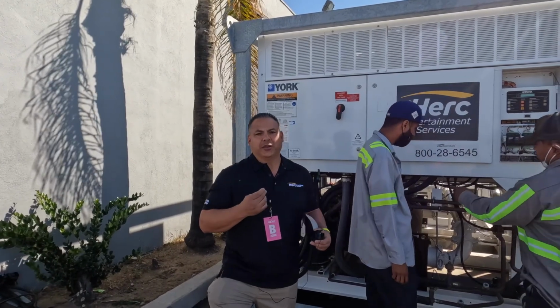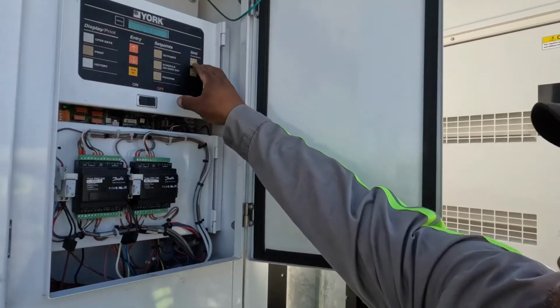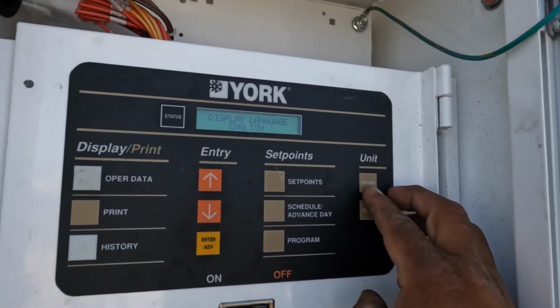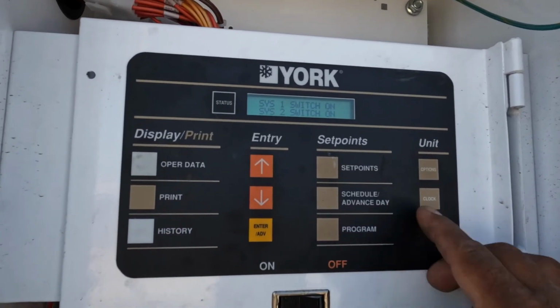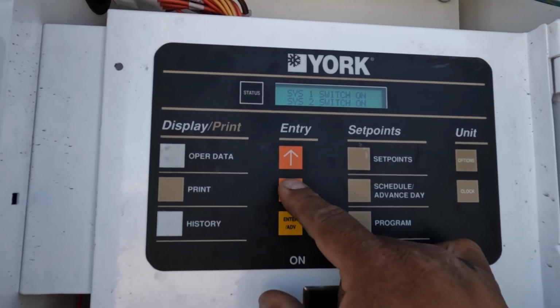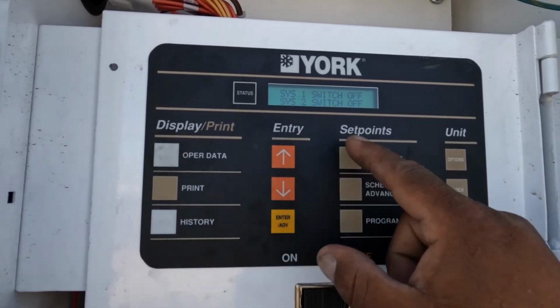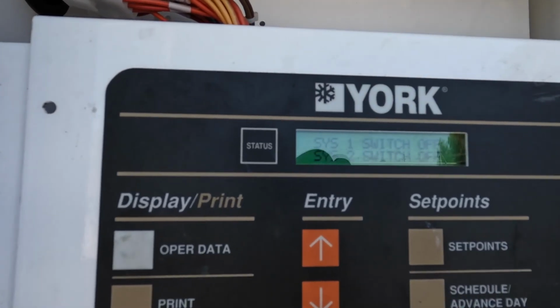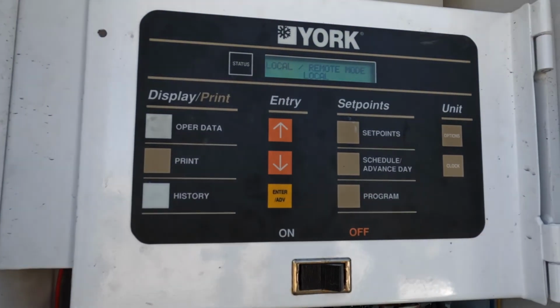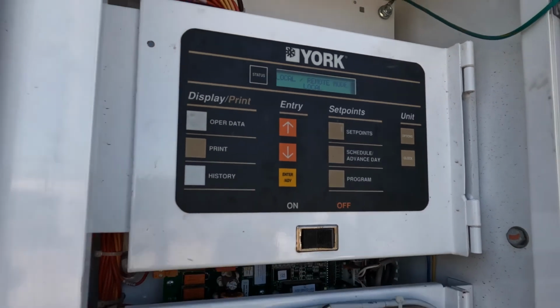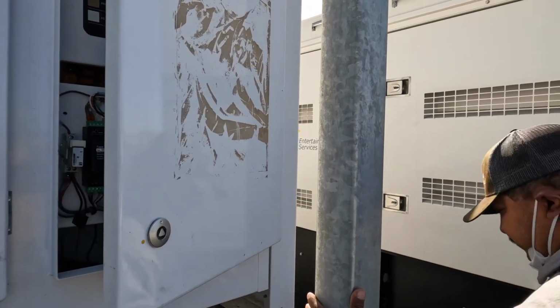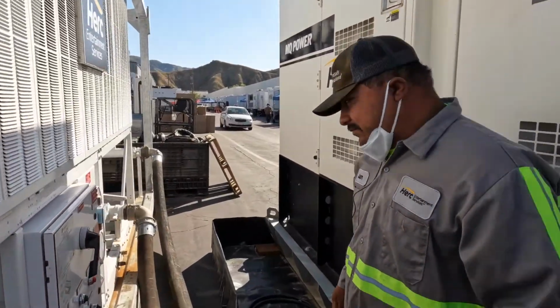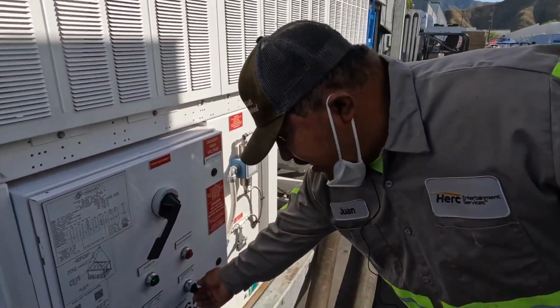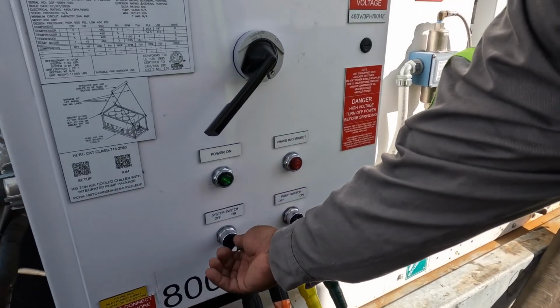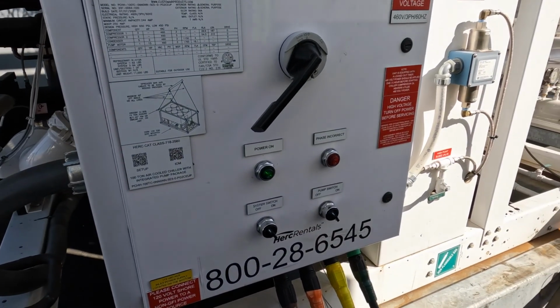Now we'll show you the shutdown procedure. The first step in the shutdown procedure is go up to options. Press options twice. Press the down arrow to where it says System 1 switch off, System 2 switch off. Press enter, and that will shut down the chiller. Now you come back to the control panel, and you shut down the pump, then you shut down the system switch, and that's about it.